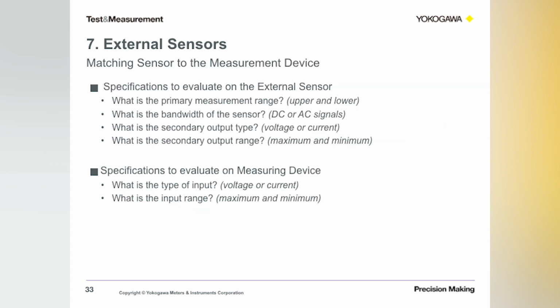So when it comes to selecting one, you really have to evaluate these and match them to your measuring device. Typical specifications you want to look at when selecting external sensors: the first is, of course, the primary measurement range, both upper and lower. Depending on your measurement requirements, you want to make sure it can measure the low signals and also the high signals that you want to. What is the bandwidth of the signal? Are you measuring DC signals or AC signals? The accuracy of those external sensors will depend on that as well. What is the secondary output type, whether it's a voltage output type or a current output type? You will want to match that to your measurement device, because your measurement device will accept either a voltage input or a current input, right?